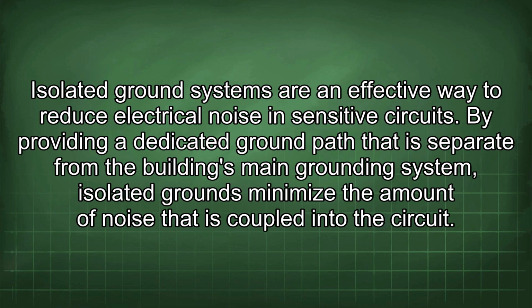Isolated ground systems are an effective way to reduce electrical noise in sensitive circuits. By providing a dedicated ground path that is separate from the building's main grounding system, isolated grounds minimize the amount of noise that is coupled into the circuit.